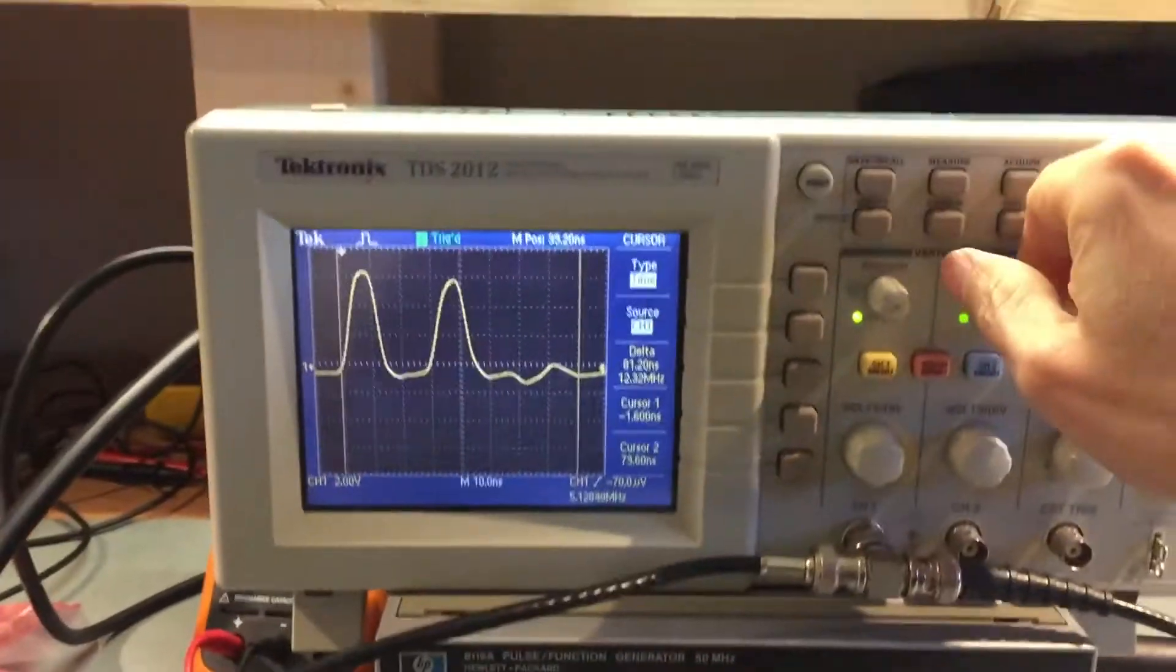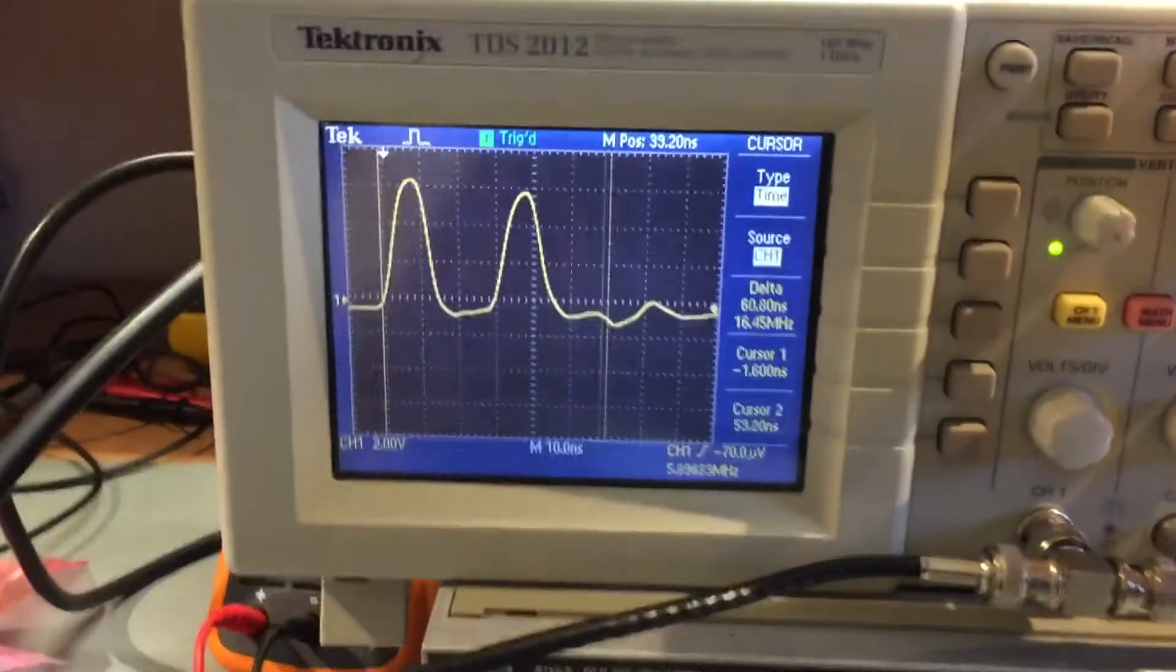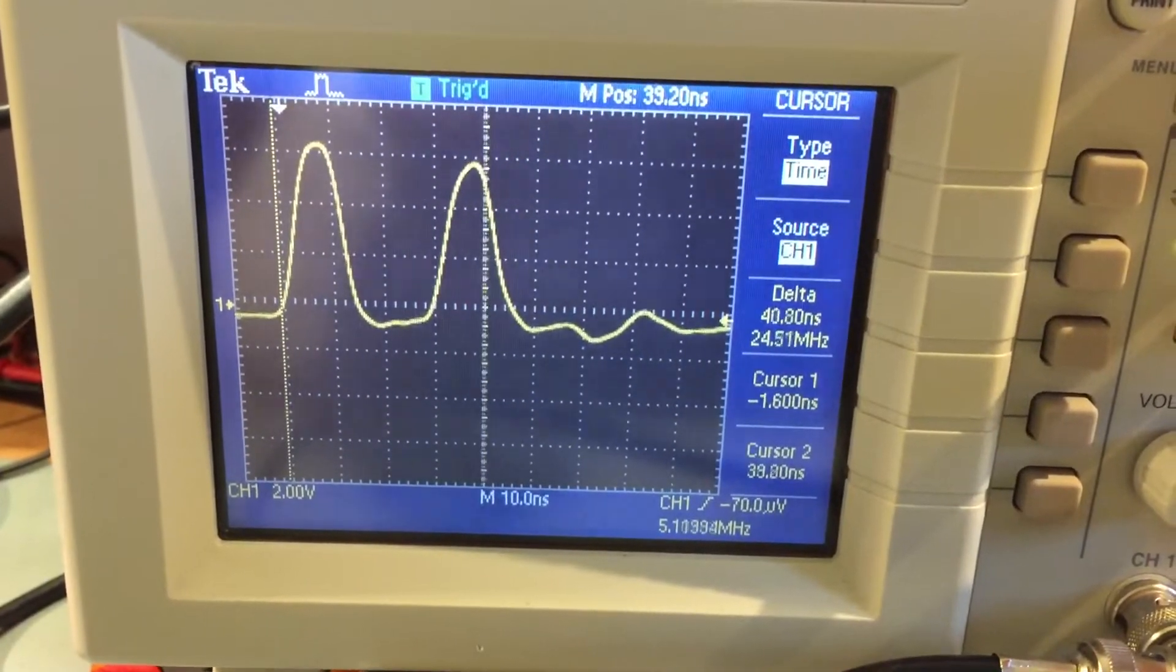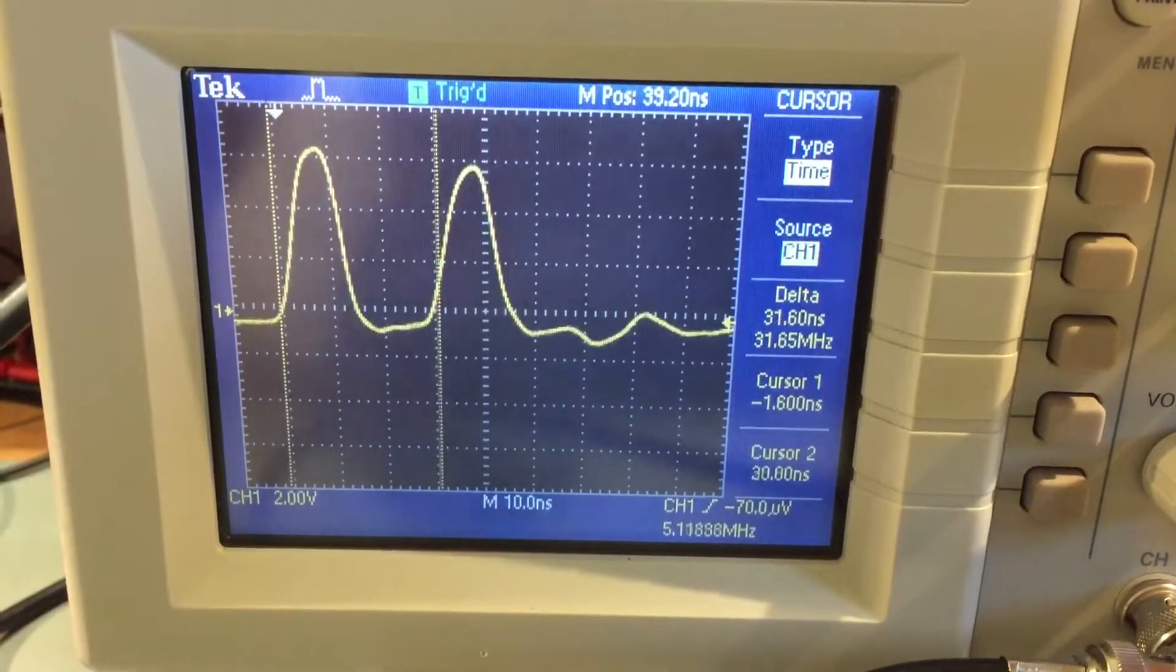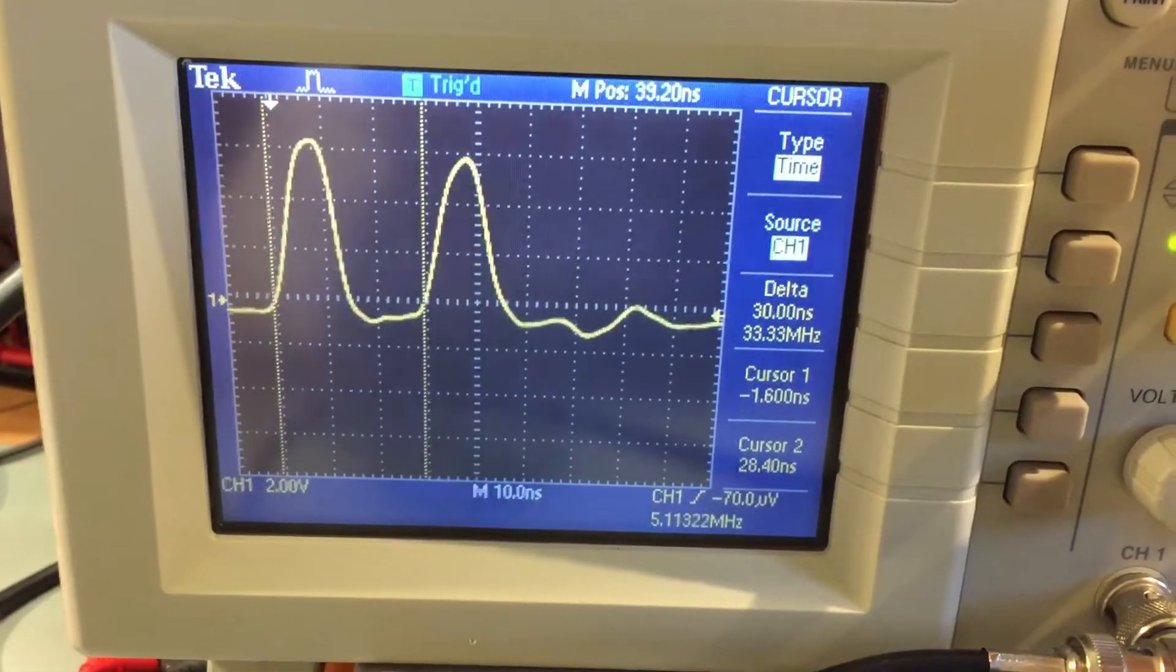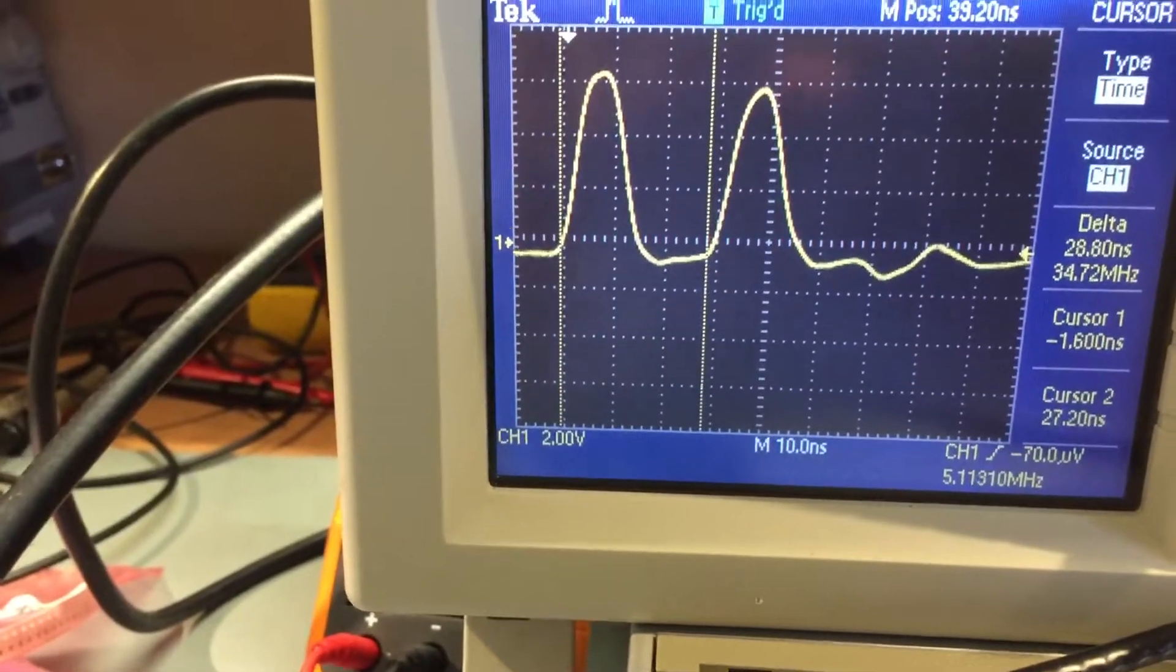I've got the cursor set up. If I turn this knob here until this vertical line, we've got the left cursor set to the start of the pulse we're transmitting. And then if we set it here, so it's at the start of our reflected pulse, we discover that it's about 30 nanoseconds.